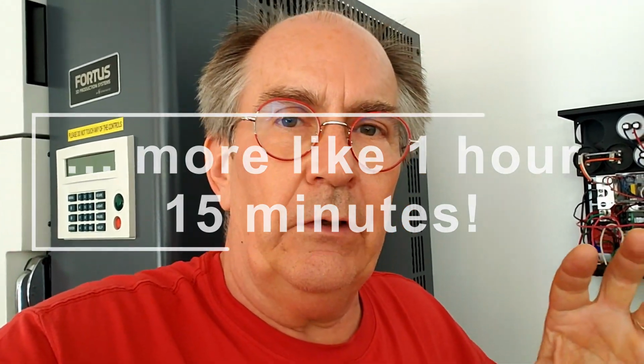And I checked the voltages, wrote them down. They should be pretty close to the voltage coming out of the sub panel, which is 243.3 volts. What I got across the connection was 241.5, 259.7, and 262.5. When I told the guy what they were, he said shut it down - he said they should be higher than the average voltage off the sub panel, but only by a couple of volts. He said something's not right.